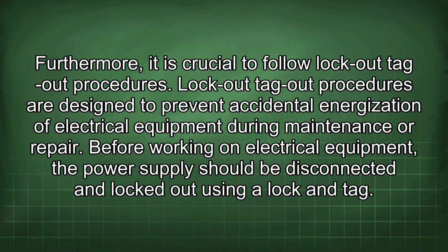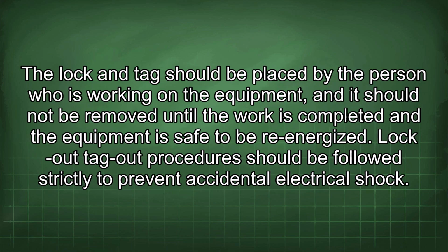Before working on electrical equipment, the power supply should be disconnected and locked out using a lock and tag. The lock and tag should be placed by the person who is working on the equipment, and it should not be removed until the work is completed and the equipment is safe to be re-energized. Lockout-tagout procedures should be followed strictly to prevent accidental electrical shock.